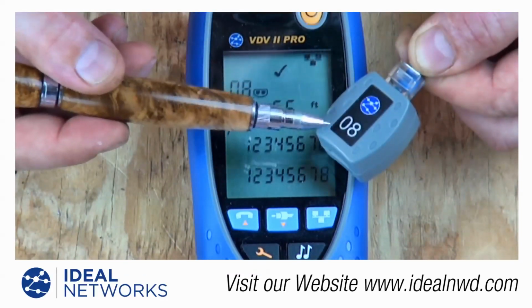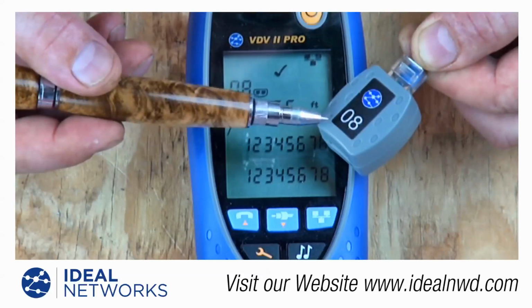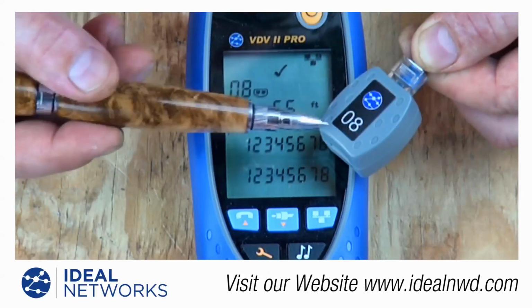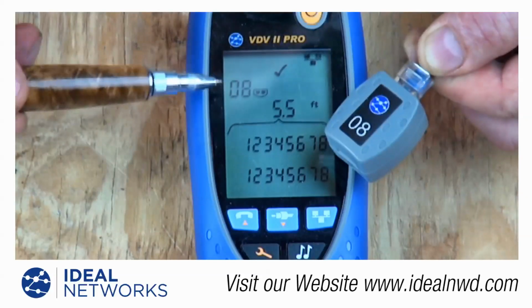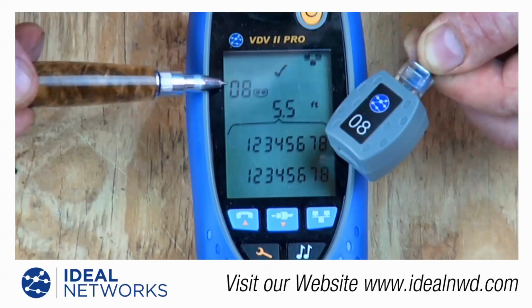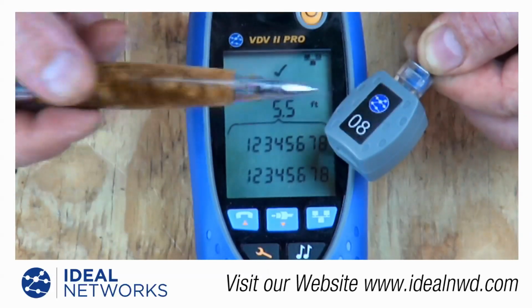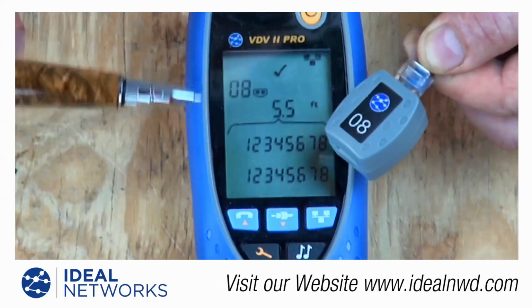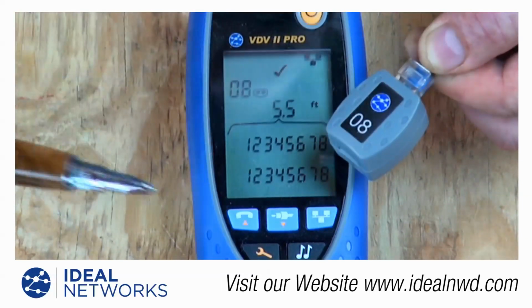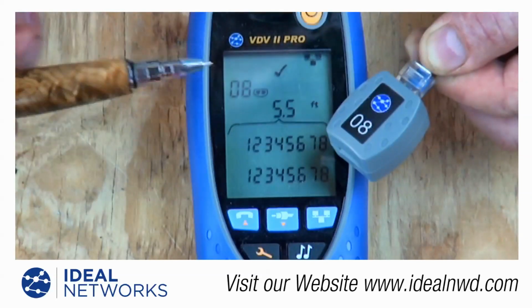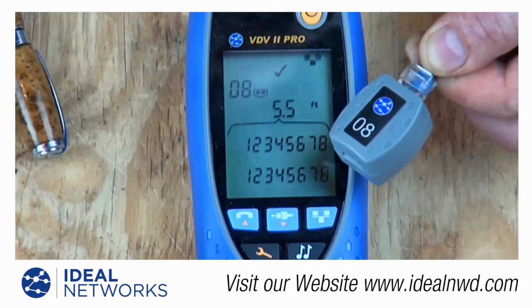By having extra remotes, if I put a remote out in, say, the foyer in the front of the office, and I do a test on the cable, the meter comes back and says pass, and it sees the 8th remote. Then I know that cable I just tested feeds that outlet in the foyer, so I can actually label my cable as I go. Very handy to have the extra remotes.